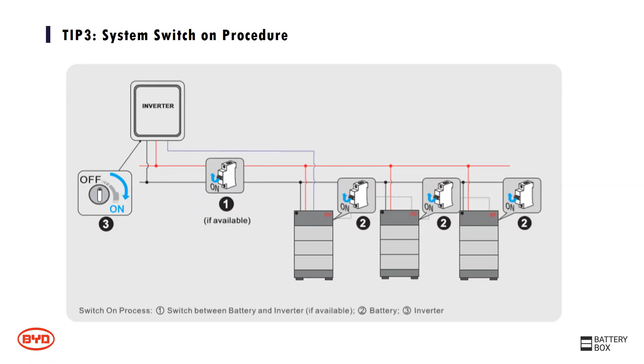And the third one is the system switch-on procedures. This is the whole system slide now, showing how the system looks. You've got multiple towers, inverters set up, and also a circuit breaker. From the battery side, we get a circuit breaker integrated, but you still have the main circuit breaker. When you turn on the whole system, firstly turn on the circuit breaker, secondly turn on the battery, and the third and last step is to turn on the inverter.